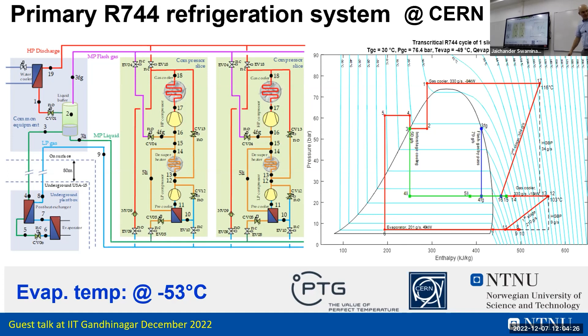They pump a lot more than is evaporating, so the heat transfer is very good. The first 30% is used, and the rest is just pumped, and as a safety also. And now we also use the CO2 system to recondense the CO2 before it's pumped back into the detector. And the challenge is the evaporators are 100 meters below, and this unit is on the surface. But it works nice, and it is now under construction, and they will replace all the detector cooling with this kind of system.